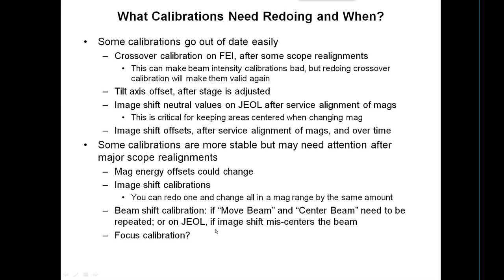Image shift offset calibration is tricky because you have to find a feature recognizable over a very wide range of mags — from say 50,000 down to 100x or 200x. The corner of a section or a rip in the film works well, as long as it's stable. A piece of ice contamination can work too, as long as you can center on it at high mag and still see it at low mags. It's actually a fun calibration — like a video game where you center a feature with the mouse, push a button, and it drops the mag and takes another picture for you to center up.